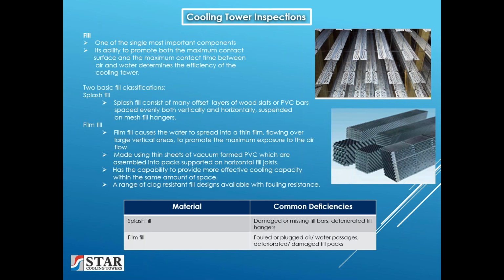Film fill is quite different from the splash fill. The film fill causes the water to spread into a thin film flowing over the large vertical areas of PVC to promote the maximum exposure to the airflow. It is made using thin sheets of vacuum-formed PVC, which are assembled into packs supported on horizontal fill supports. These film fills have the capability to provide more effective cooling capacity within the same amount of space. This is why, when we talked earlier about a 30-foot fill height compared to possibly a 5-foot fill height in the counterflow tower, that is the result of the high performance of these film fills. And there's a range of clog-resistant fill designs available today with fouling resistance.